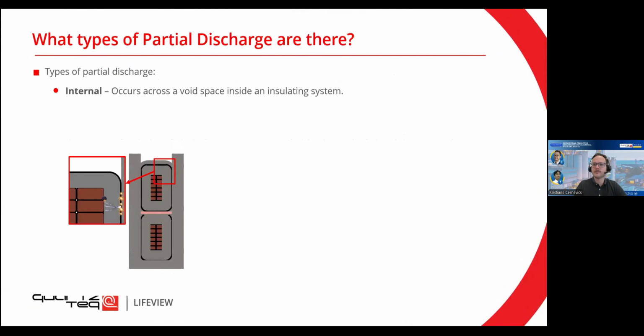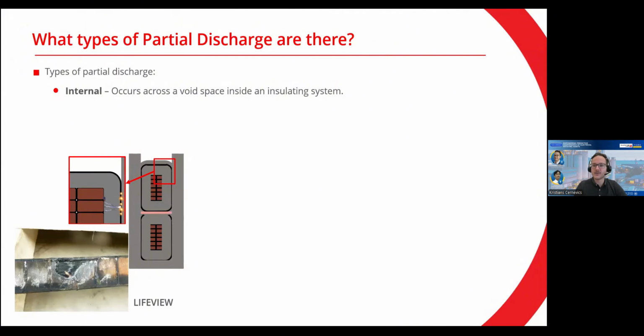So what types of partial discharges are there? Usually we classify them into three types. First of all, there are internal discharges. For example, here you can see a slot discharge. There are small gaps in the slot where the electrical field can reach high values, and these small gaps are then traversed by a discharge. This can lead to some serious consequences. If this is not spotted, which it usually is not because it's internal, you have quite high degradation of the insulating material.